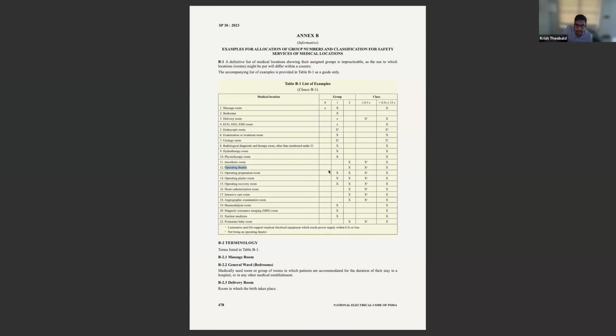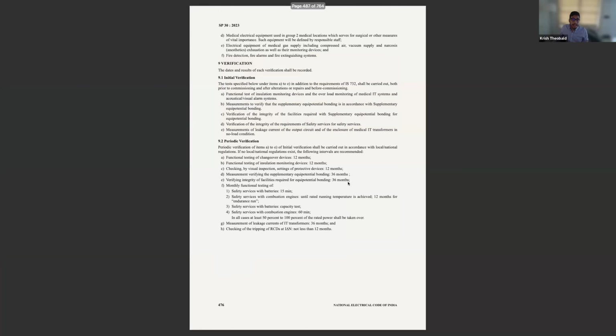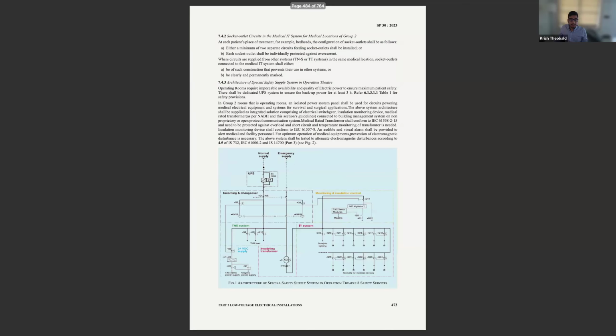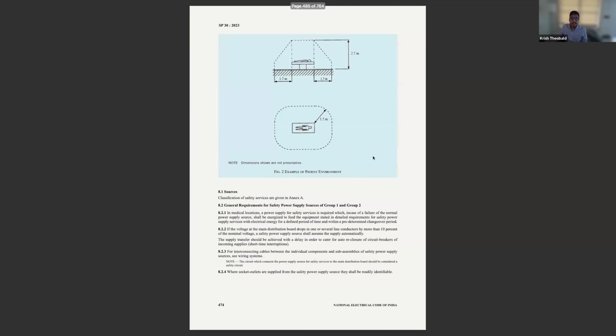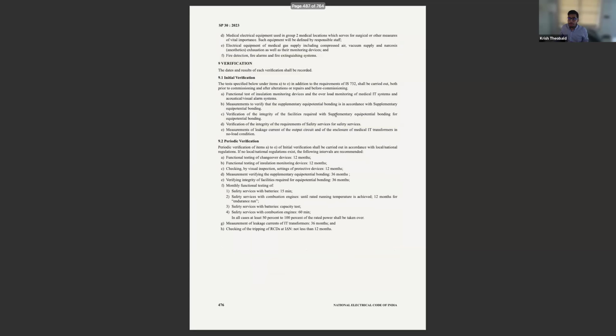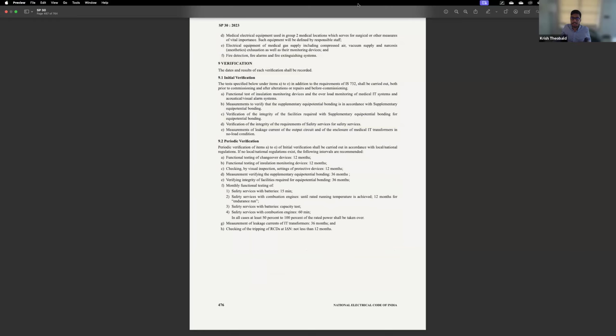For example, an operating theater is a group 2 location. An anesthetic room is also a group 2 location. ICU, the intensive care room, is also a group 2 location. In group 2 locations, the requirements for electrical installations are completely different. Like Mr. Gopakumar said, you need an IT system. There may be certain group 1 and group 0 locations where you can use an RCD, and then it is a requirement also, so you need to use the right type of RCD. But in group 2, you're not allowed to use an RCD as per the standard, because you cannot have disconnection in an operating theater. That will cause a hazard to the patient. Thank you.